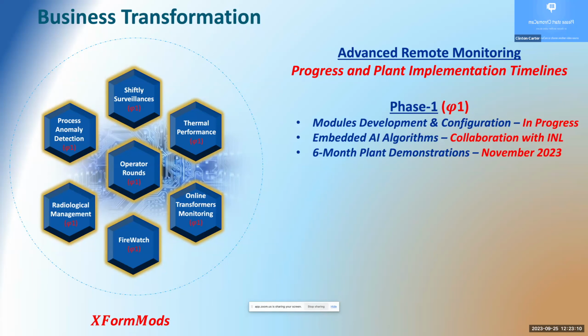To give you a sense of one or two of these: shiftly surveillances. Every 12 hours we send operators at my power plant in Texas, Comanche Peak, into over 100 rooms and compartments to manually read a temperature on an analog gauge bolted to the wall. Quite time consuming. We are installing wireless temperature transmitters as part of this project, so instead of spending all those man hours every day, we will click on the application from the control room. Those sensors will light up, send their data, evaluate it against the acceptance criteria, and print out our surveillance report with zero human effort.